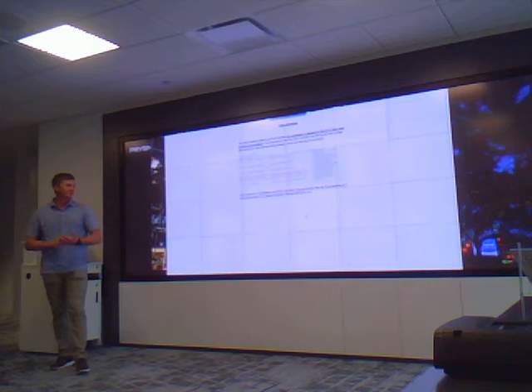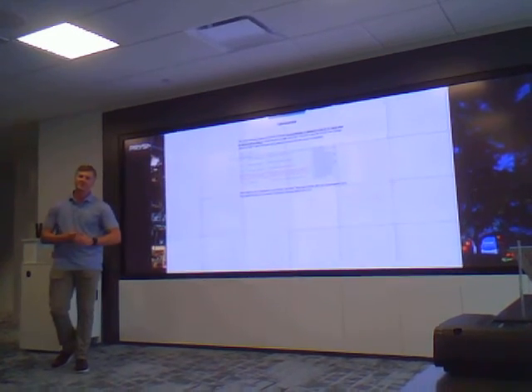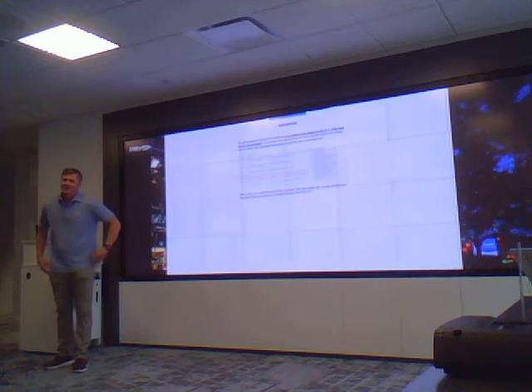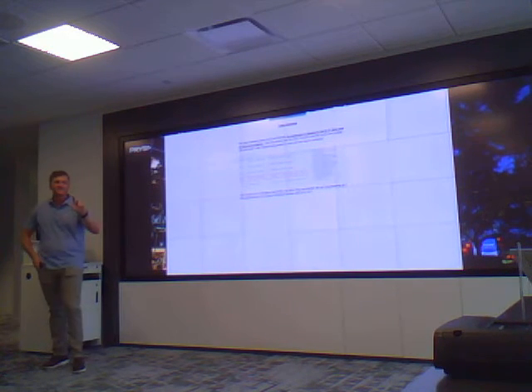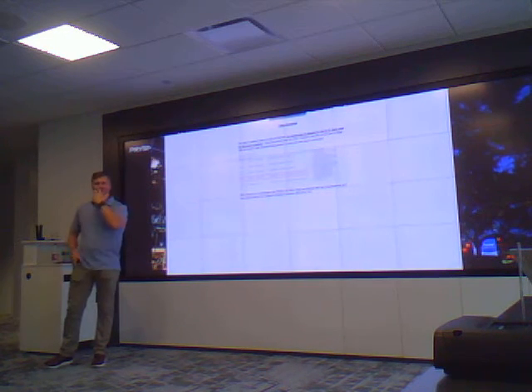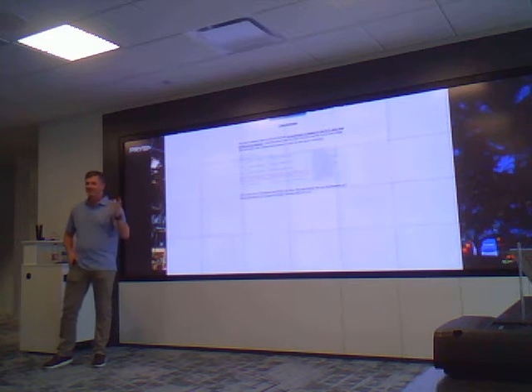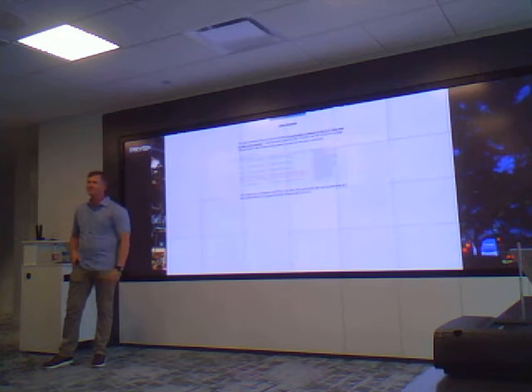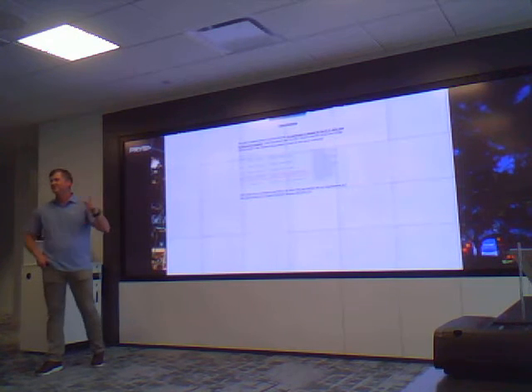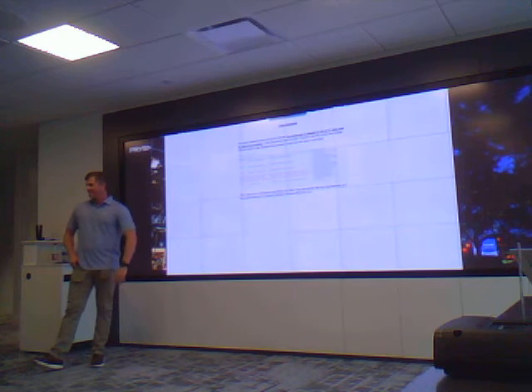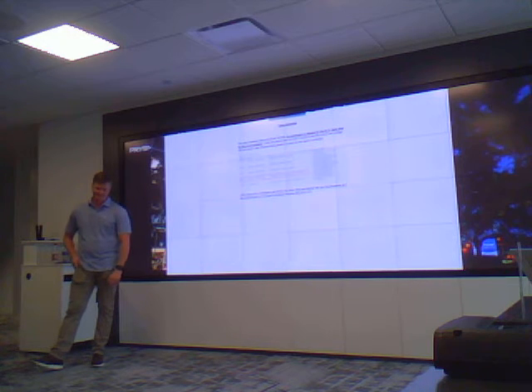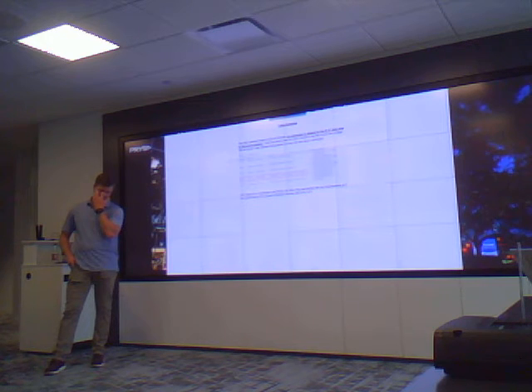Back on the comm wire topic, I went to a site to commission it after the contractor installed it, and right when I opened up the DZC, there was 18-2 wire in there for the comm wire. Needless to say, they had to re-pull all of the communication wire between each one. The only thing we accept for a comm loop, with no exceptions, is 24 single pair. It may work fine that day, and even the next week, but it will degrade over time, and you'll watch it start failing more and more.